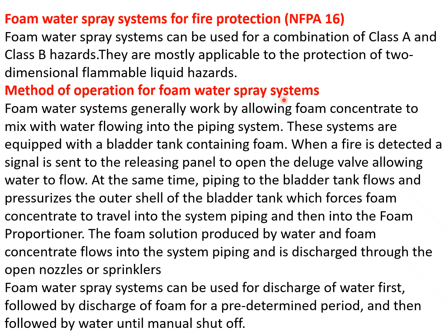Friends, I am now discussing the foam water spray system for fire protection as per NFPA 16, which is an American standard. The foam water spray system can be used for a combination of Class A and B hazards. They are mostly applicable to protection of two-dimensional flammable liquid hazards. The next portion of this we have already discussed.